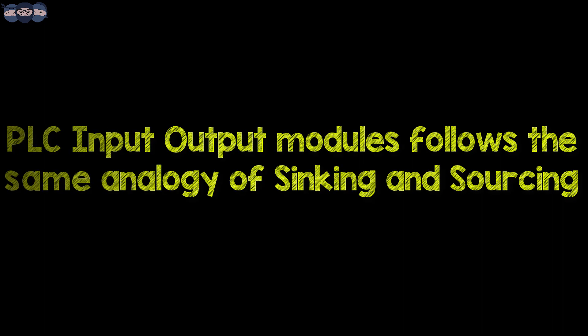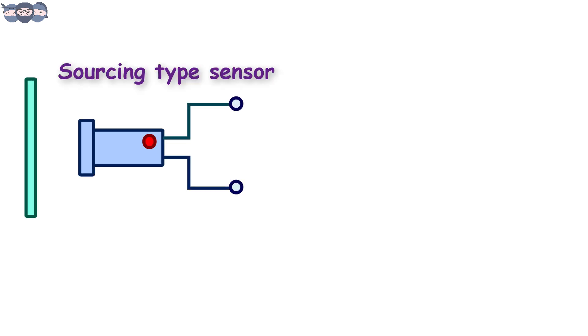The same terminology is used to denote the sinking or sourcing types of input or output modules of a PLC or a controller. If one has understood the circuit diagrams explained, it would be clear that if a sensor is sourcing type, then the input module required would be a sinking type.